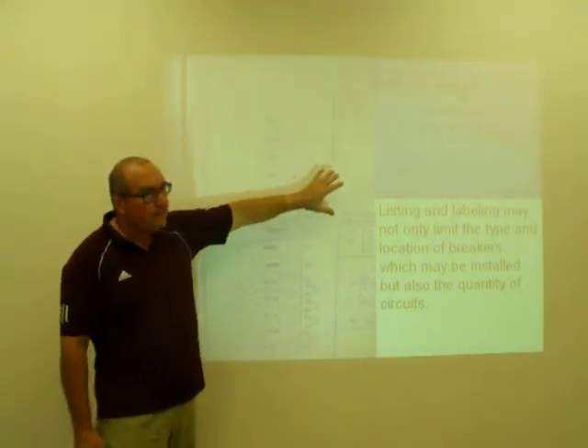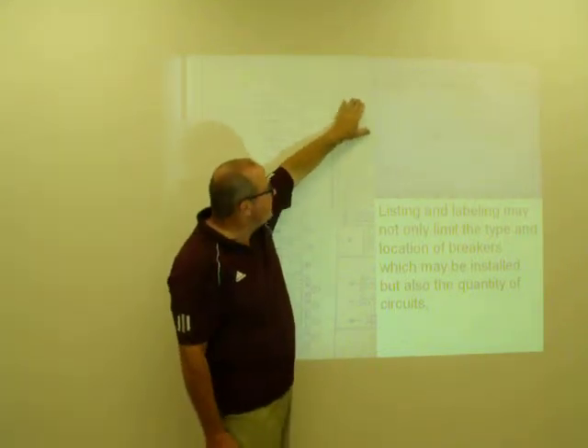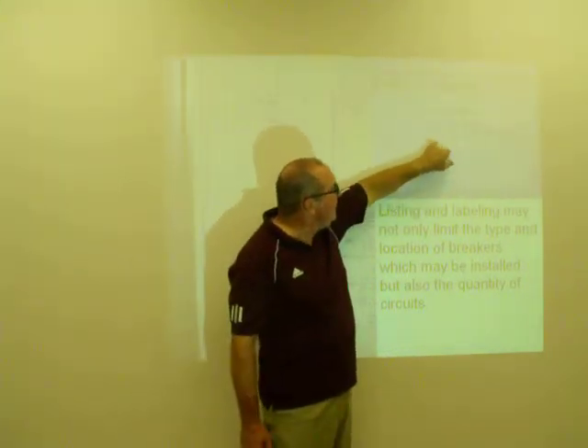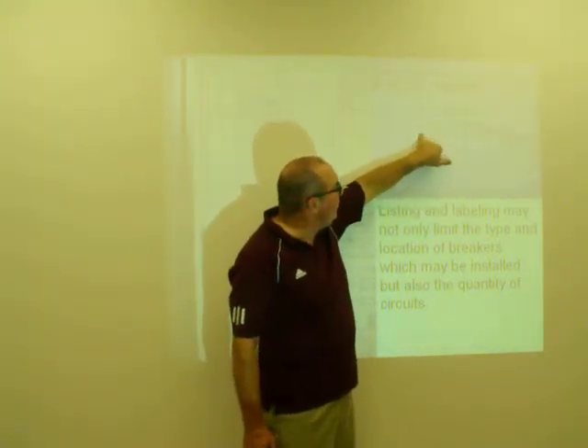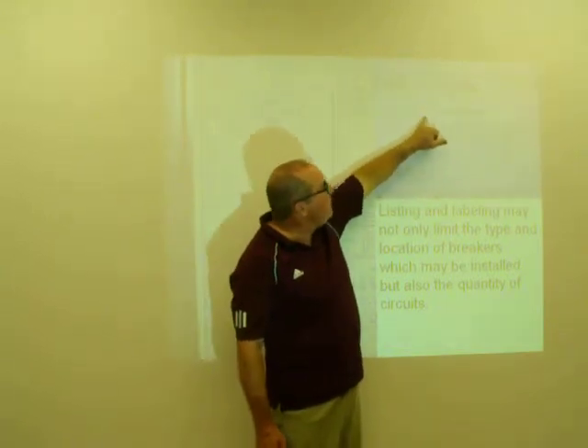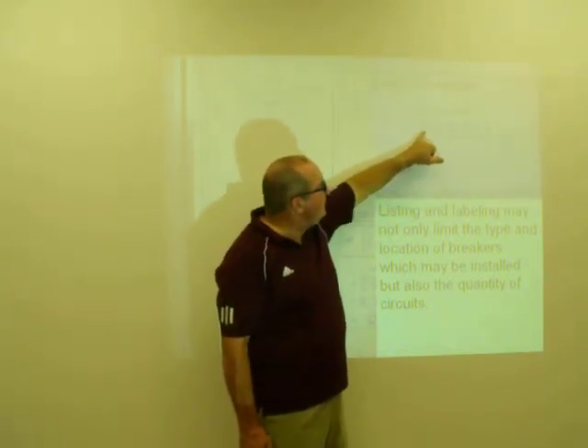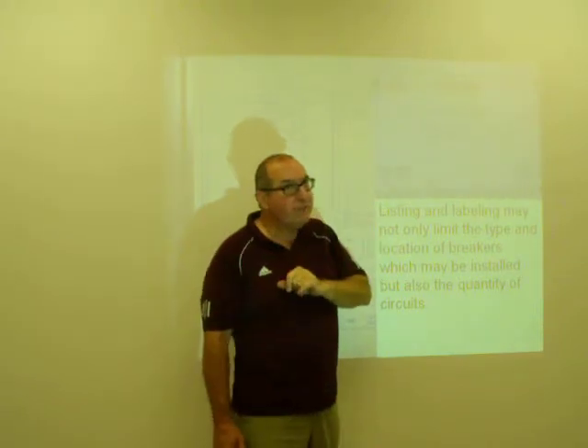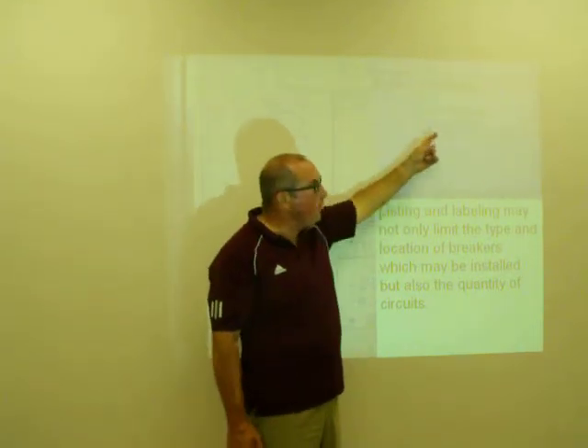And in the listing also, in a different part, which you can't see as part of this diagram, there will be something up here that will tell you 20 poles maximum. And then it tells you the limits in terms of the size of the breakers you can install depending on the type of wire that you're installing.